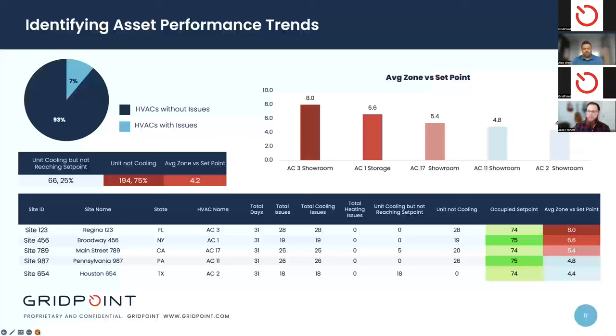And we can categorize these in different ways. We not only quantify the performance of the unit, but we also qualify it. So we can look at the units that are cooling effectively but not reaching set point, meaning the supply air temperature is cool, but the zone is still trending above the configured cool set point. And then there's unit not cooling, which would be a higher severity issue, meaning the supply temperature is not sufficient to condition the space, and the zone is above the cooling set point.